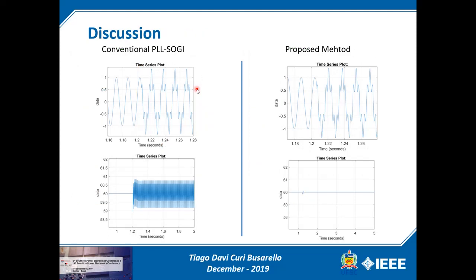A short comparison between the proposed method and the conventional PLL based on a second-order generalized integrator. When the input signal is clean and sinusoidal at 60 Hz, both methods perform well. However, when the input signal has harmonic distortion, the PLL shows an oscillatory behavior around 60 Hz with relatively high values. On the proposed method, the frequency is estimated accurately even in the presence of harmonic distortion, showing that this method is attractive and effective.